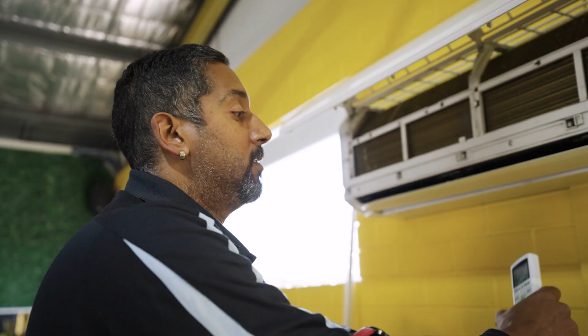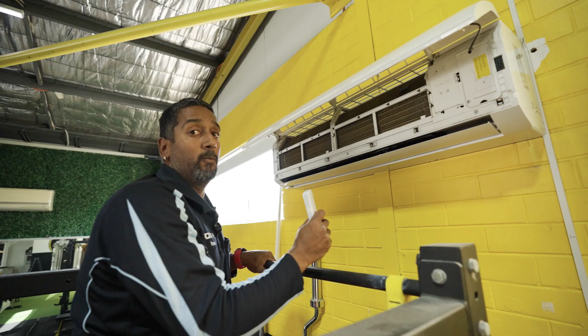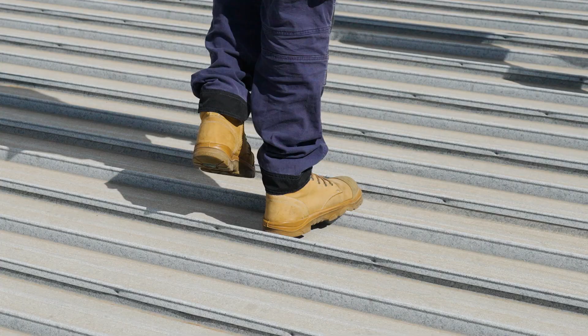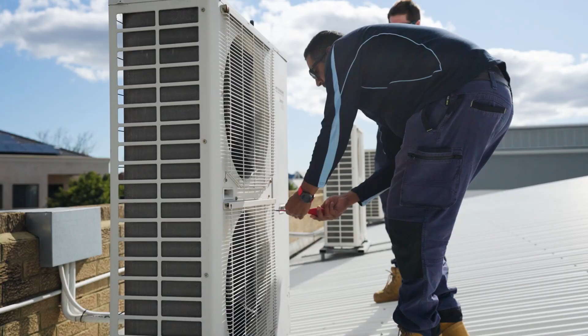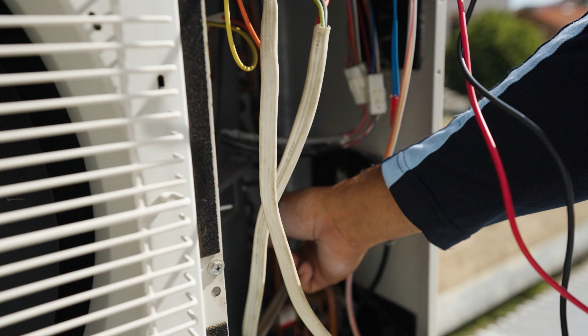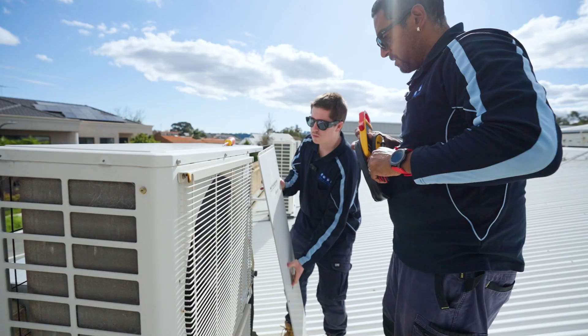So we're just turning it on full fan speed and 32 degrees because we want to stress the unit and make sure it's operational. And the fan blade doesn't look too dirty. We'll just go to the outdoor unit and see what it's doing while this fires up. So this is your main power cable here. Yeah. How you know that is it goes down to your switch. So that turns the unit on and off. So we just want to test if there's power on that cable to know if we can run this unit. And we have 240 volt power there.